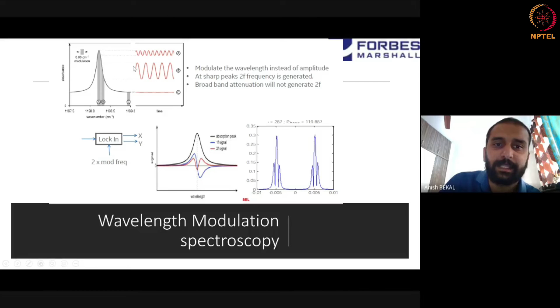because the slope of the absorption line is practically linear. And then in the region where there is a sloped curve, there is some amount of 2f generated, and you get a spectrum something like this. There are a lot more characteristics of this spectrum, but I'll not go into that for the sake of time. This peak is now proportional to the absorbance peak. And the very nice thing about this is that you can control the span of the wave number that you are scanning with every 10 kilohertz that you apply.